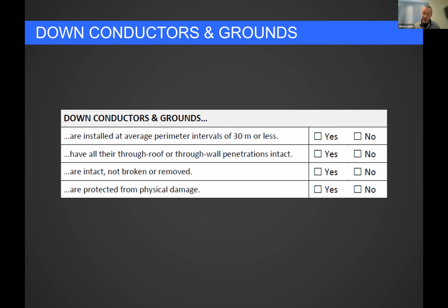So the reason we have multiple paths to ground for every lightning rod is we want to divide that current up. Maybe we could shove 200,000 amps of current through a single down conductor, but we don't want to try. We want to give it as many paths to ground as possible so that current can divide, and then we take it down to ground. Functionally speaking, yes, Martin, I will get to you in just a second.